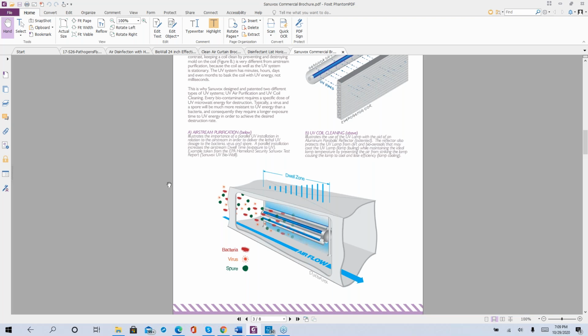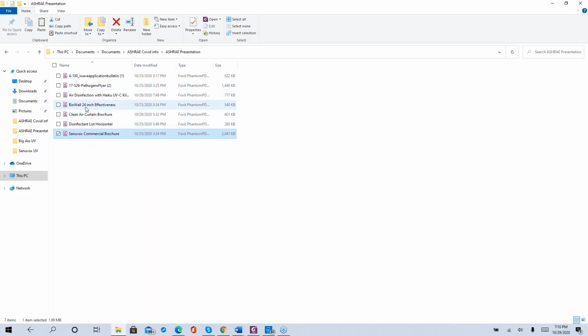You can treat anywhere from 2,000 CFM upwards to 40,000 CFM based on proper sizing guidelines that the manufacturer provides. And you can mount multiple of these bulbs within the larger duct. Let's say that you've got, for example, 100 by 24. So you might have two different bio walls of say 30 or 36 inches in length. They do go all the way up to 48 inches of length in order to get to your CFM.